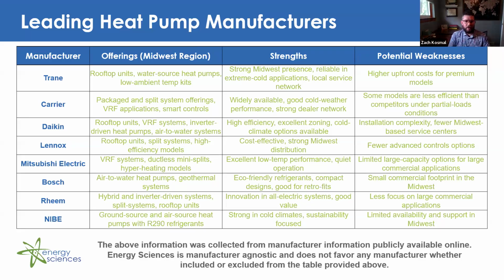So for example, if you're looking to install a retrofit split heat pump system, if you look at this table, Carrier, Lennox, or Rheem may be a good option because they all provide those split system offerings. An alternate option could be a ductless mini split heat pump offered by Mitsubishi Electric, for example. So another example or situation, maybe a large multi-zone rooftop unit nearing replacement I mentioned earlier. This would be a great opportunity to install a VRF system. So if we take a look at this table, Daikin, Carrier, they both offer VRF systems as options. And those would be good to replace that multi-zone traditional rooftop unit serving multiple zones within a facility.